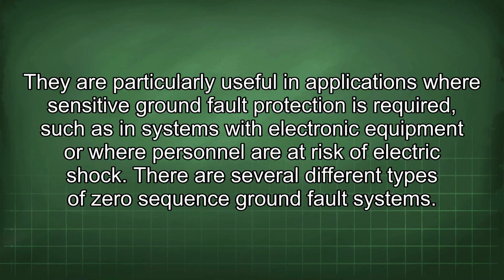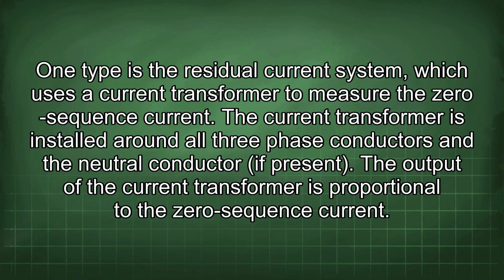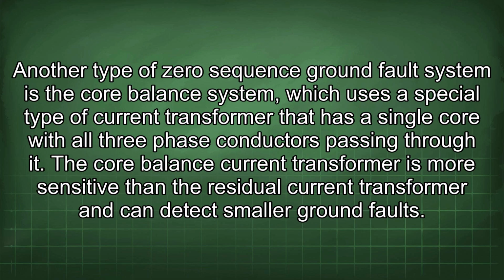There are several different types of zero-sequence ground fault systems. One type is the residual current system, which uses a current transformer to measure the zero-sequence current. The current transformer is installed around all three-phase conductors and the neutral conductor if present. The output of the current transformer is proportional to the zero-sequence current. Another type is the core balance system, which uses a special type of current transformer that has a single core with all three-phase conductors passing through it. The core balance current transformer is more sensitive than the residual current transformer and can detect smaller ground faults.